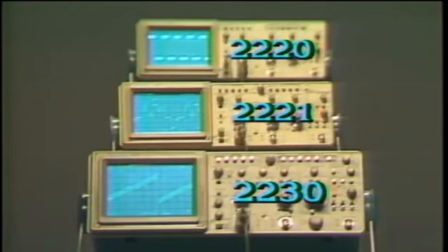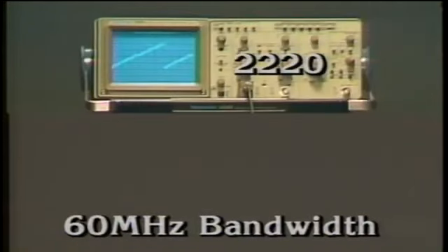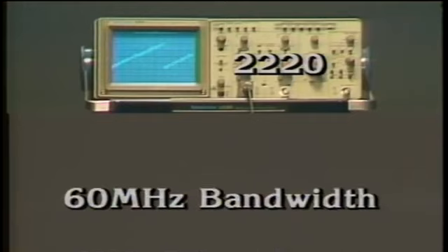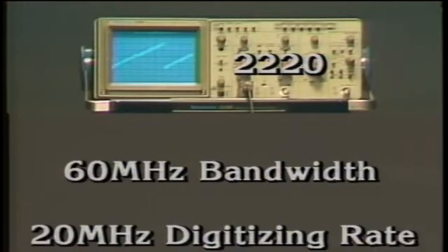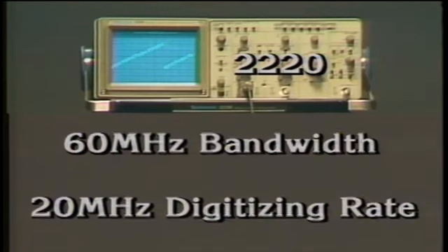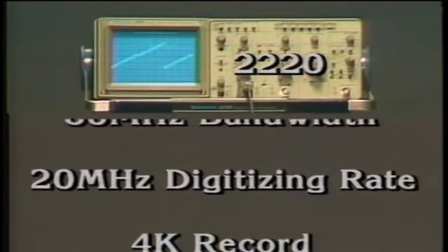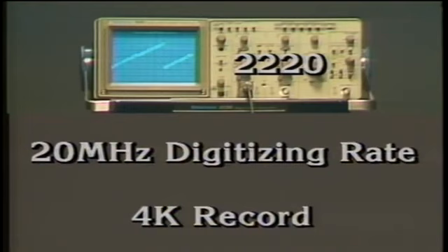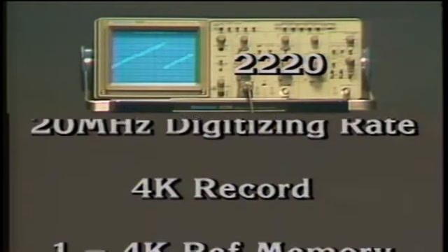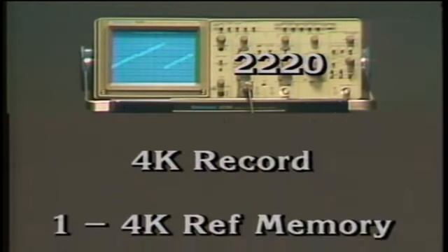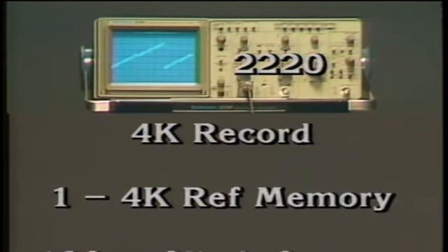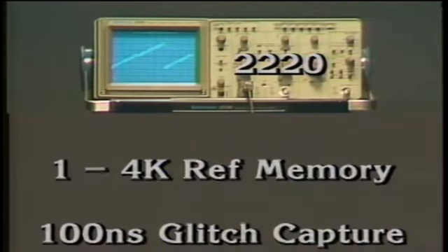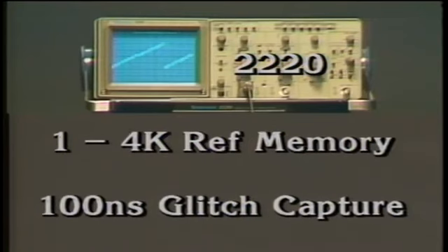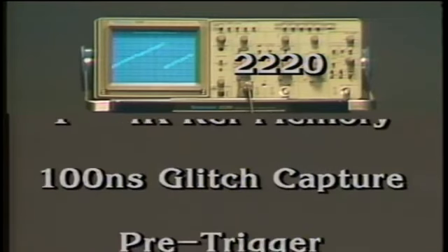One of these instruments will be the answer to your measurement questions. Let's review these three products and their major specifications. The 2220 has 60 megahertz bandwidth both in analog or non-storage mode and in digital storage mode for repetitive waveforms. With a 20 megahertz digitizing rate, all of these scopes will record 10 points per cycle on a 2 megahertz sine wave, single shot. The 2220 has a 4K record length. That is, each digitized waveform is stored as 4,096 points. It can store one 4K waveform in a reference memory.